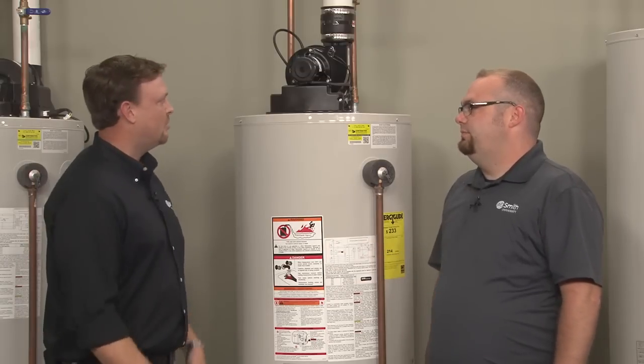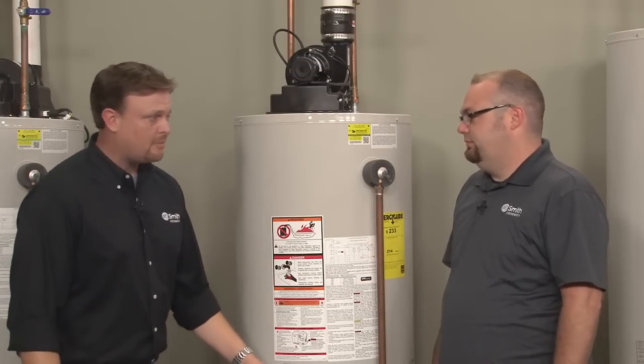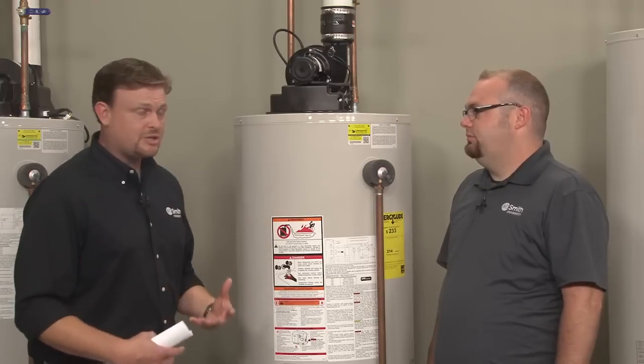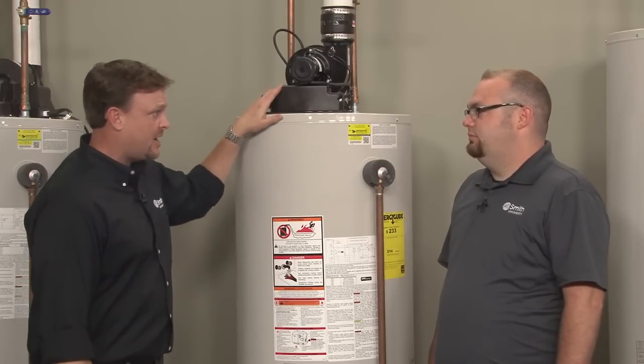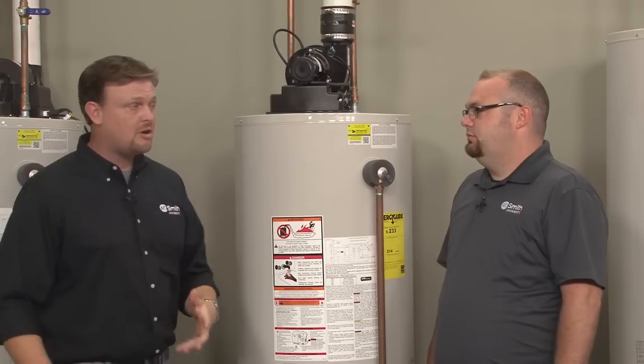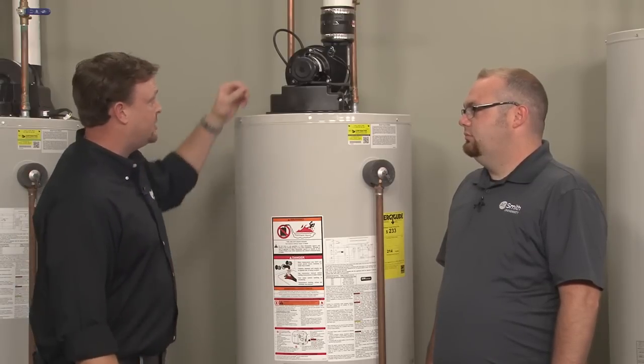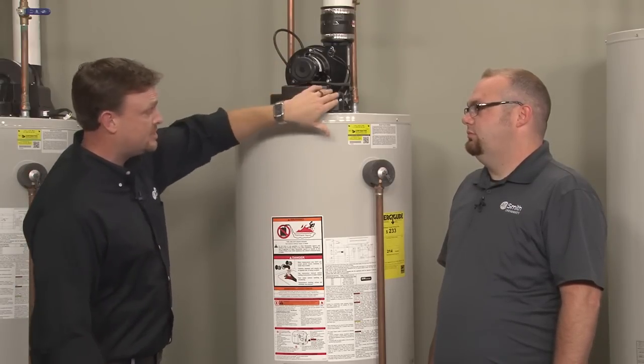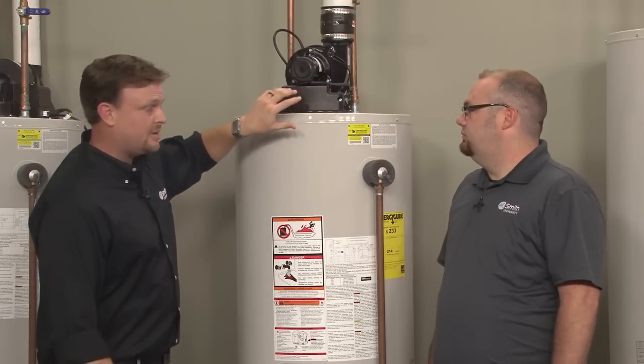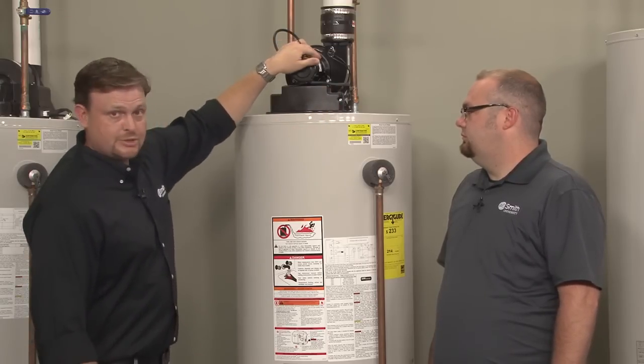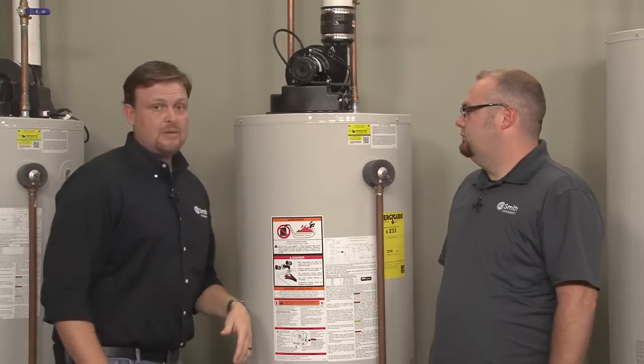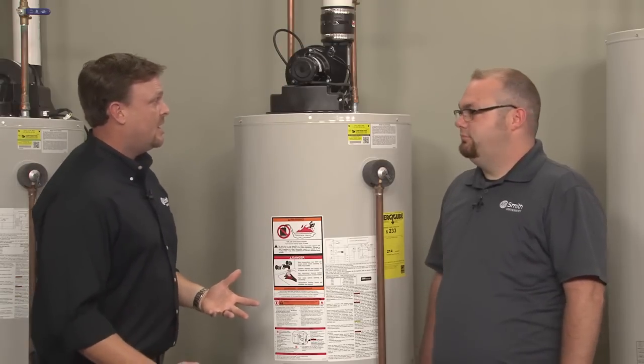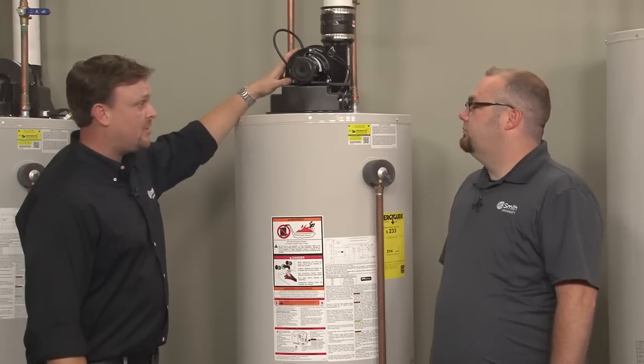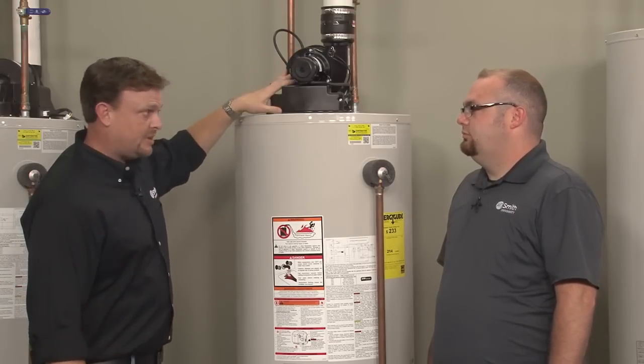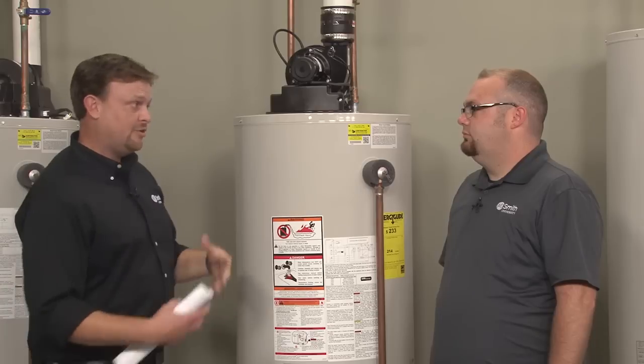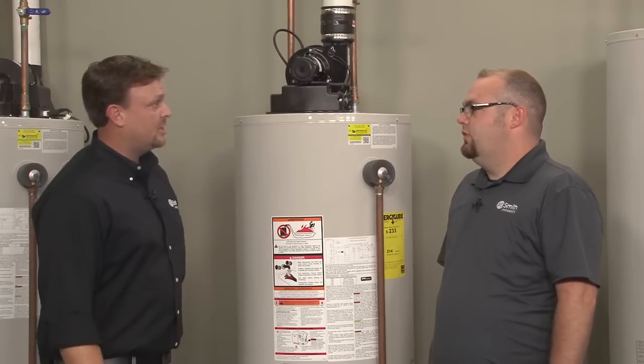Okay. So go up to it, turn it off, turn it back on. If the blower does not start, I'm going to try a new capacitor. Correct. If the blower does start, then we start getting into checking our venting, checking all the hoses, the connections, make sure the switch is connected properly, your high vent temperature switch is connected properly. Then we're going to go ahead and check our pressure. If the blower is pulling enough vacuum and your venting is correct, then that's the switch. If it's not and your venting is correct, then we're looking at maybe the blower.